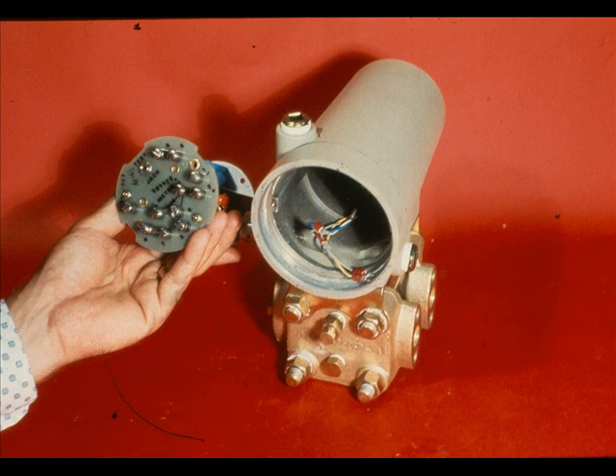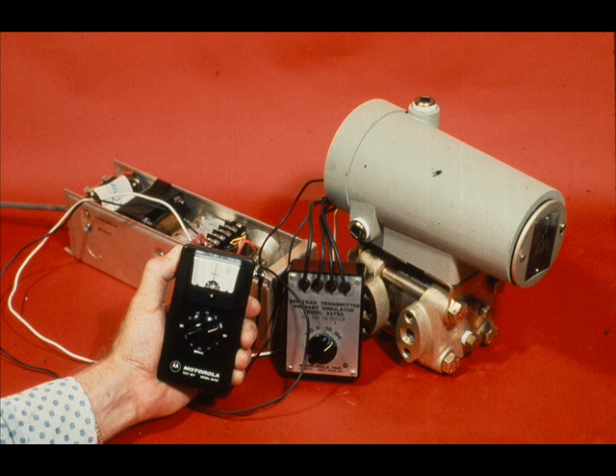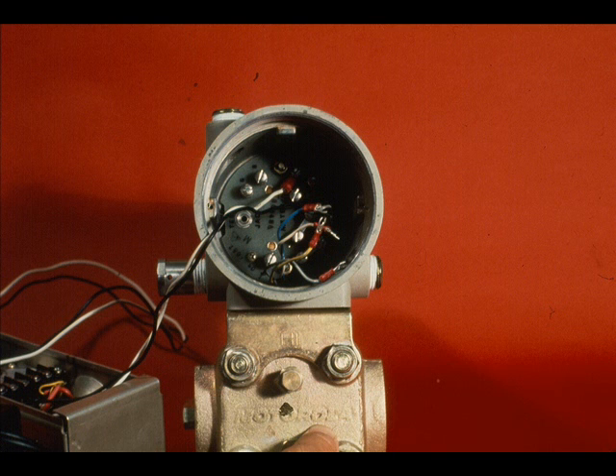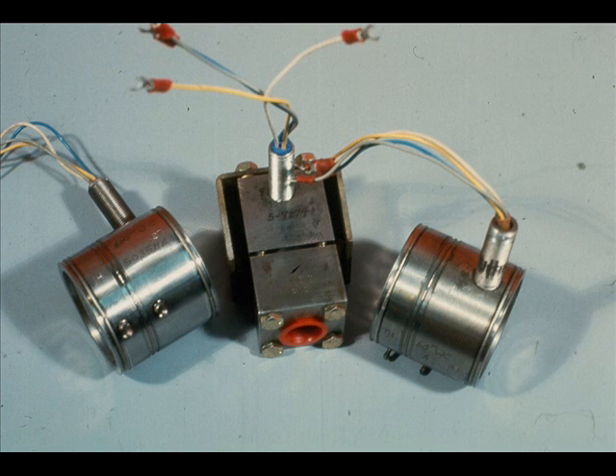If the transmitter does not respond to the cell simulator, the amplifier is defective and should be replaced. If the transmitter responds correctly to the primary cell simulator and still will not perform when the amplifier is reconnected, the trouble is in the measuring cell and it will have to be replaced.